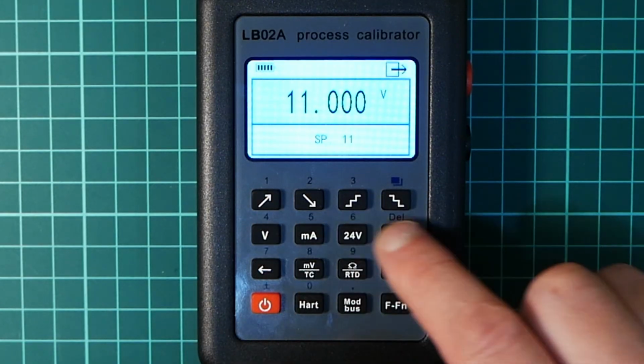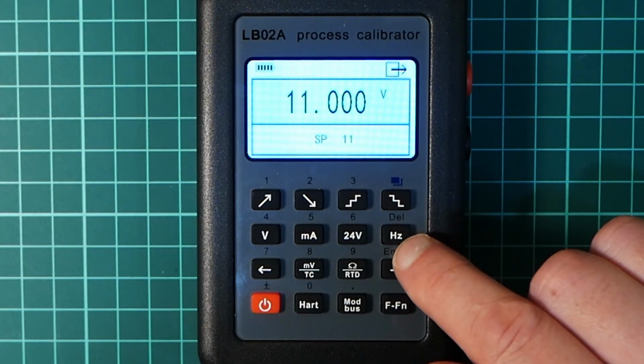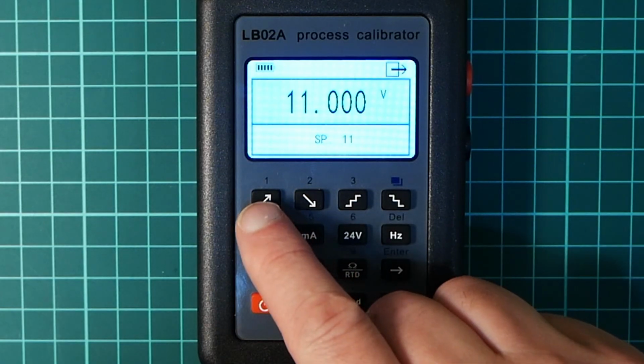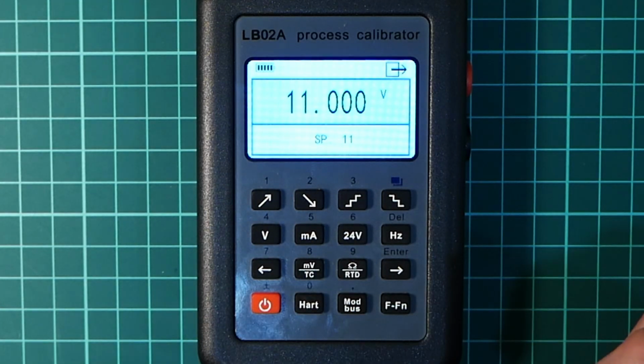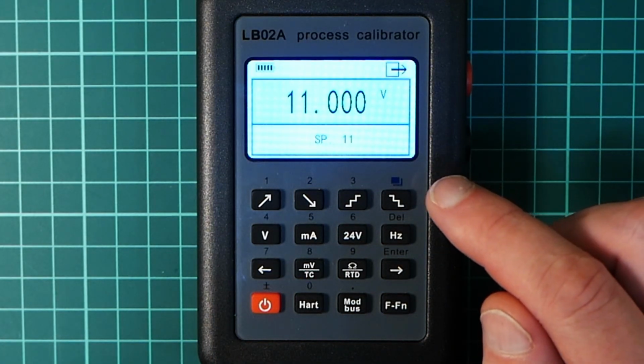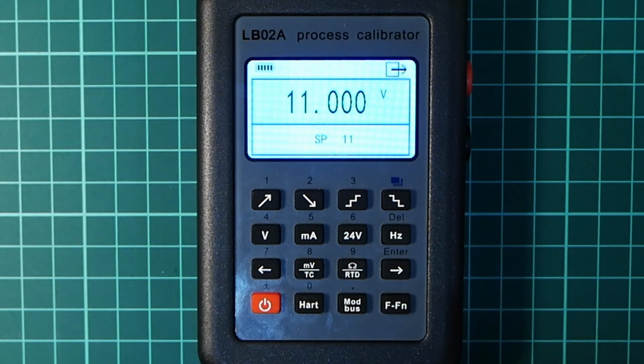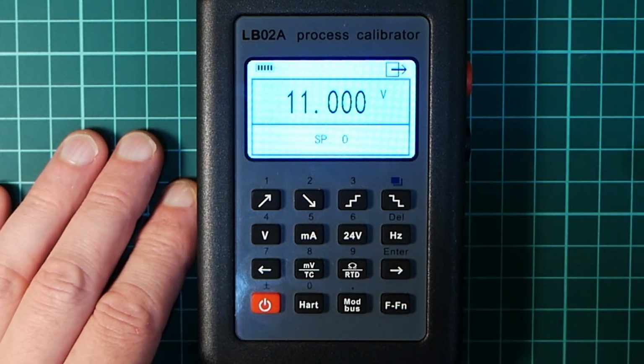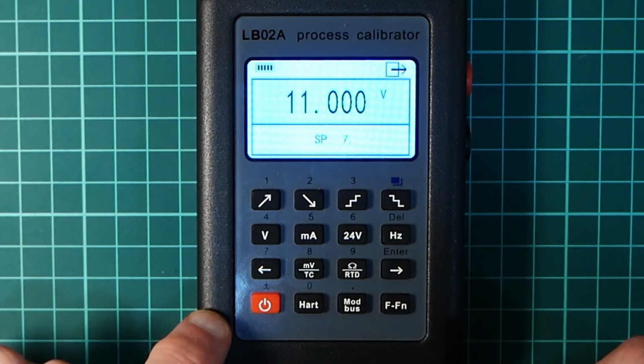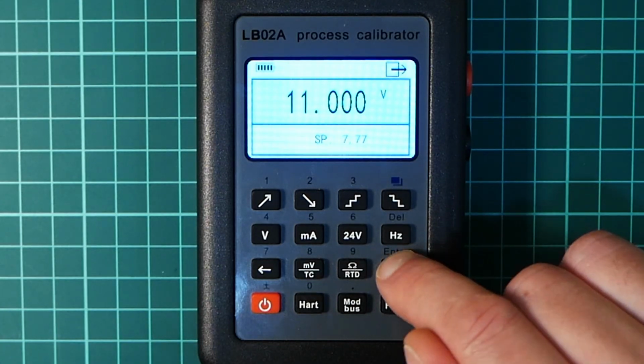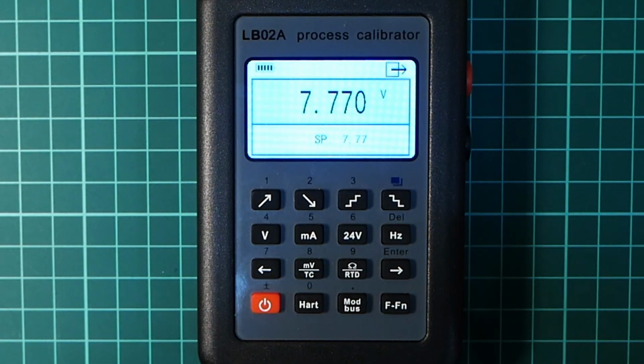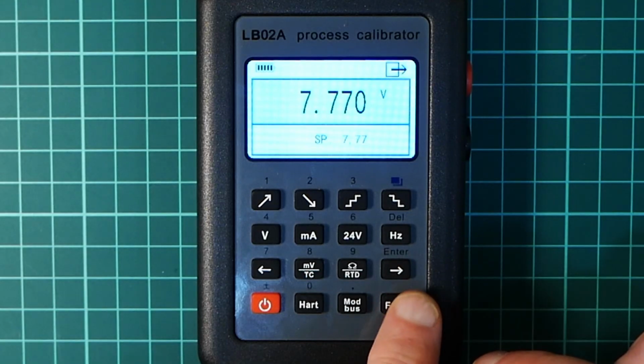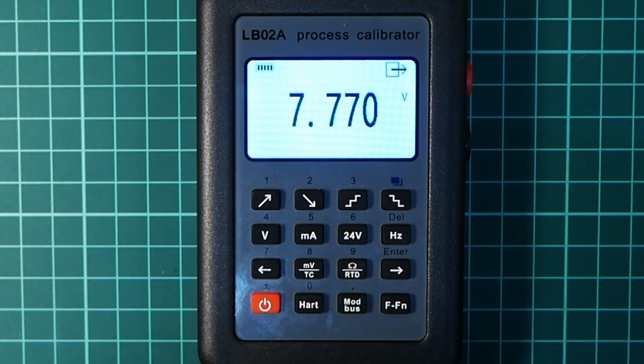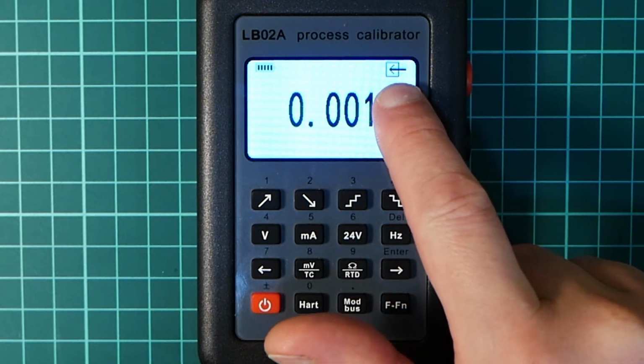In function mode, all these push buttons have a secondary use. Let's say the hertz push button is now delete, yes, and on all of these are numbers, but it's also not great because they put black numbers on a dark gray background, so it's kind of hard to see. Okay, I delete the set point and enter, let's say, 7.77, and I press enter. So right now we have a specific voltage. We can go out of function mode by pressing function again. So right now we are sourcing 7.7 volts. Now if we want to measure, we press voltage again. You see this arrow goes to the left side. So right now we are inputting voltage.